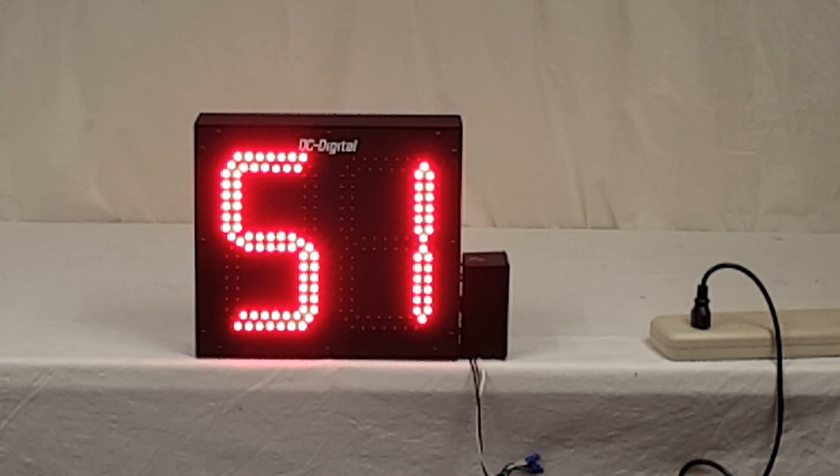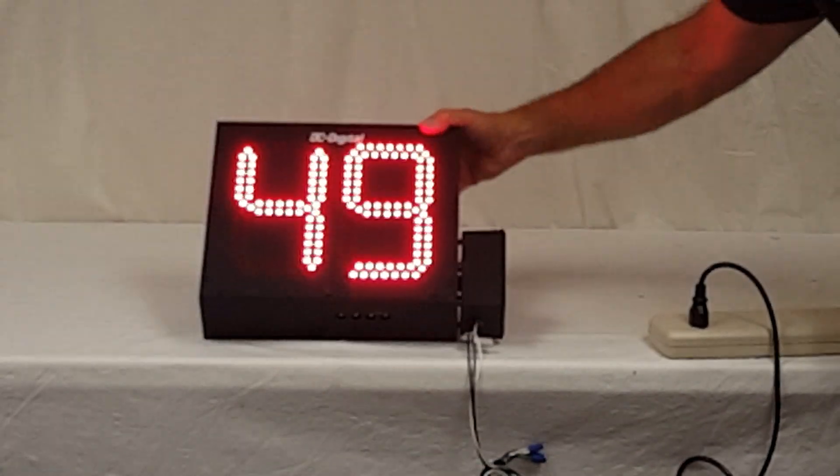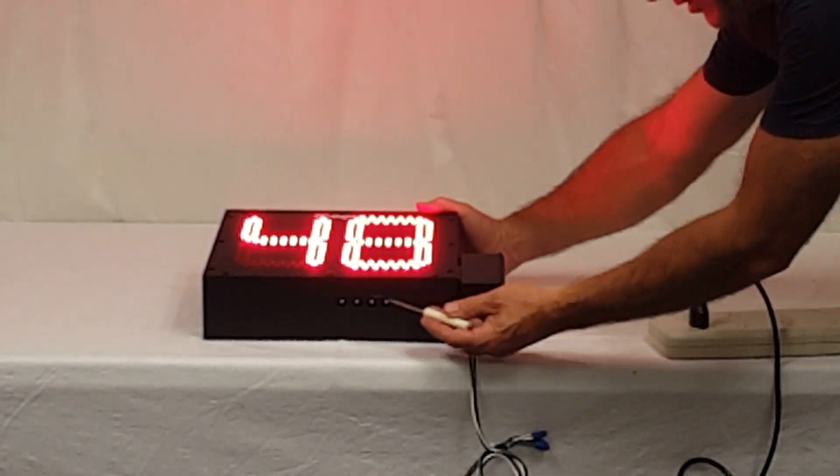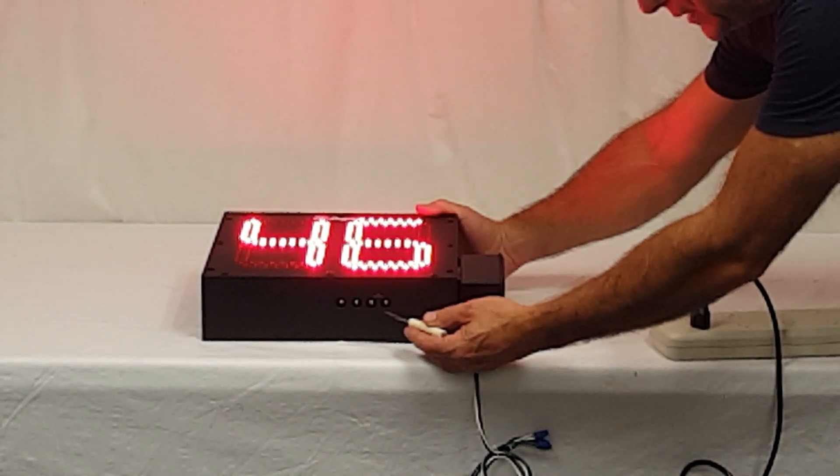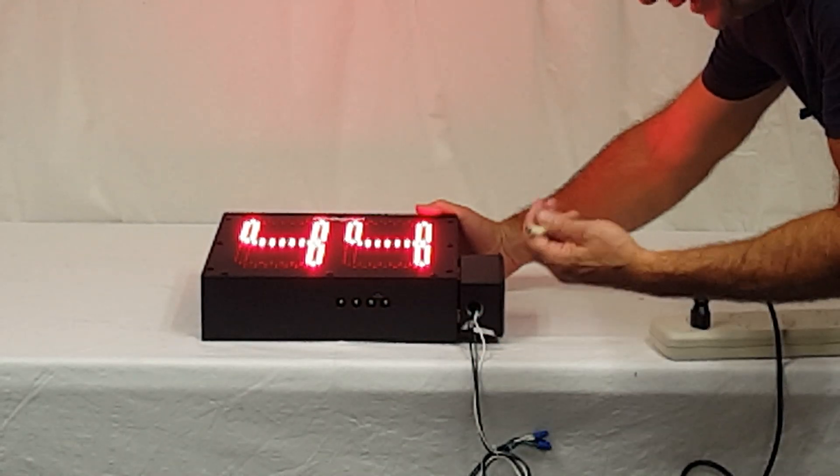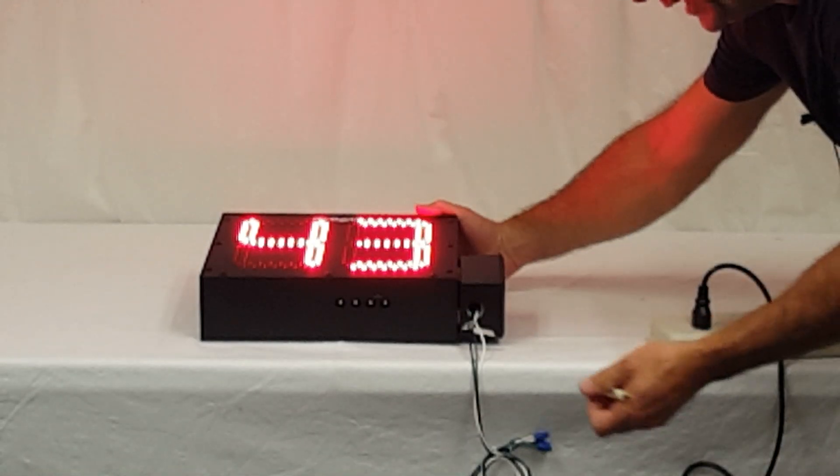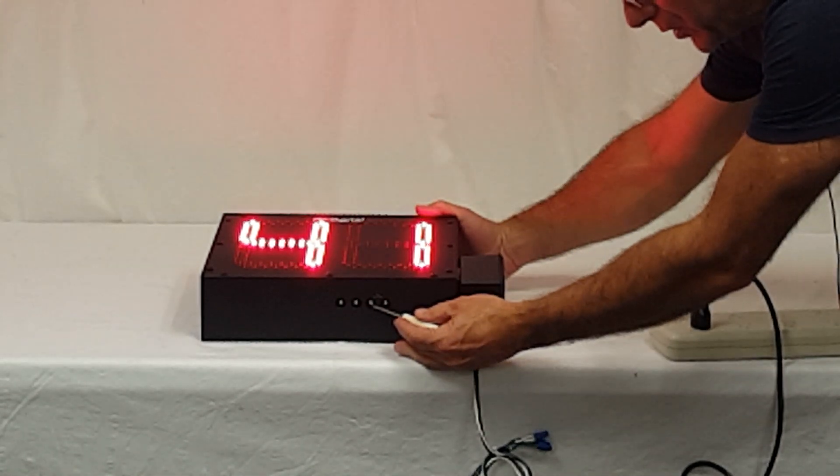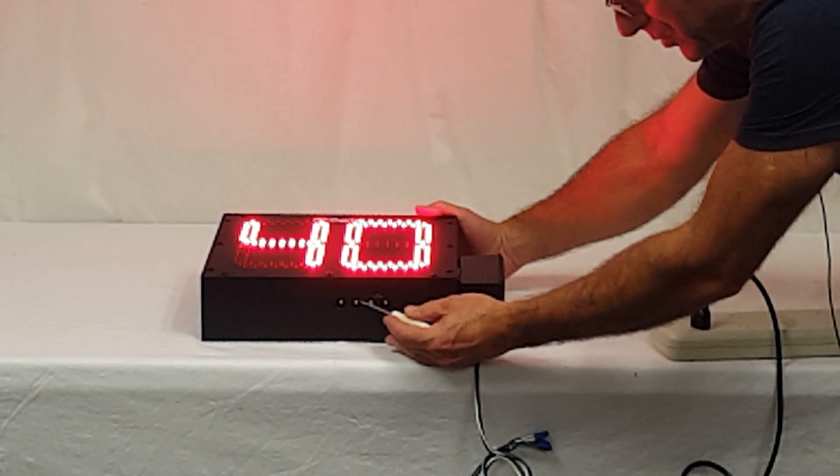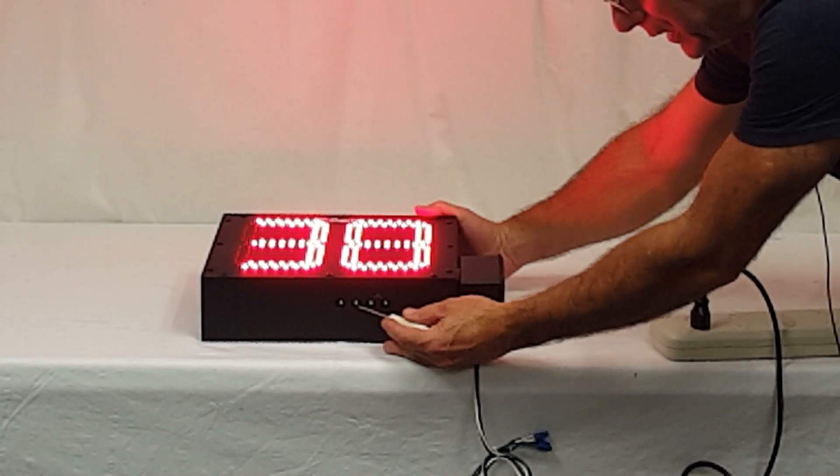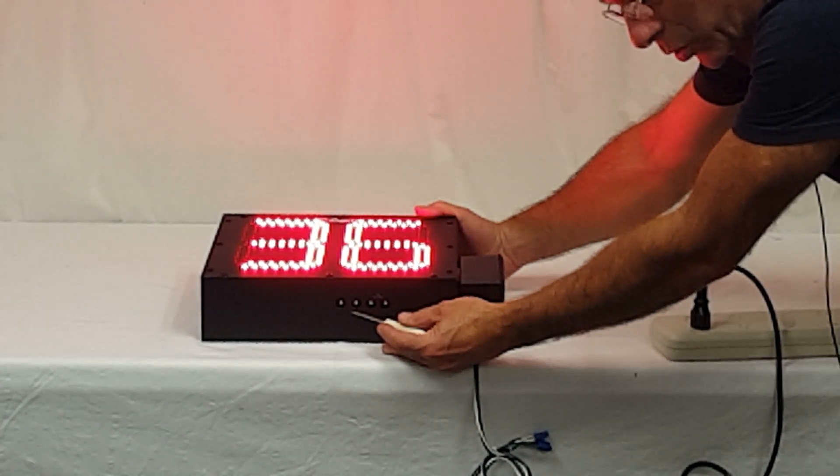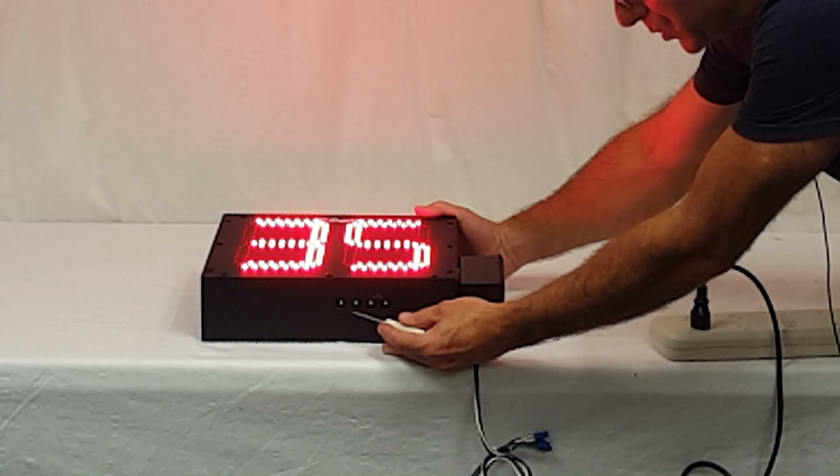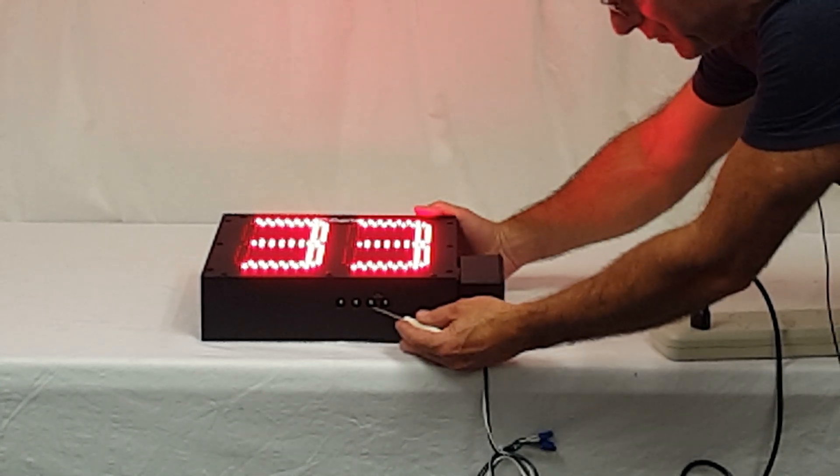To set the timer, there are rotary set switches on the bottom. They're BCD, what we call BCD set switches, and they have detents and go from zero to nine. It's just for these two here. These other two are non-functional. Normally that's what our normal BCD switches are for, four digit, but we have two.